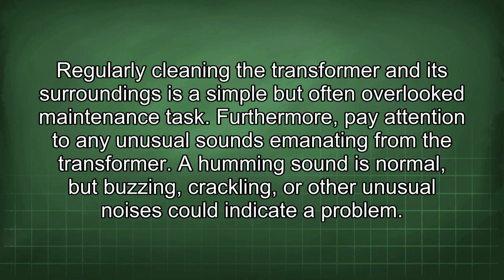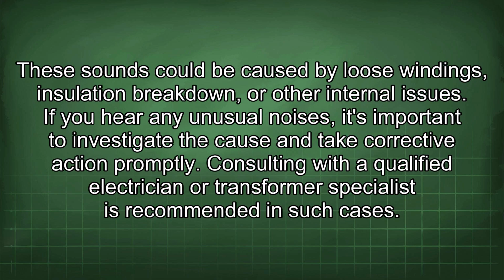Furthermore, pay attention to any unusual sounds emanating from the transformer. A humming sound is normal, but buzzing, crackling, or other unusual noises could indicate a problem. These sounds could be caused by loose windings, insulation breakdown, or other internal issues. If you hear any unusual noises, it's important to investigate the cause and take corrective action promptly. Consulting with a qualified electrician or transformer specialist is recommended in such cases.